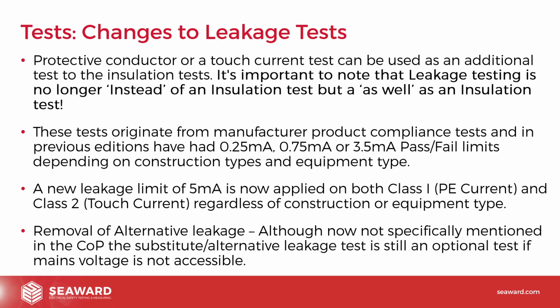The new leakage limit for the 5th edition code of practice is now 5 milliamps, and this applies to both Class 1 and Class 2. So it's just a 5 milliamp limit, whether that's a PE current test or a touch current test, whether it's portable, handheld, movable, stationary, whatever the type of equipment is. We now just do a leakage test, and the limit is 5 milliamps. So we've got a 5 milliamp leakage limit applied to everything. That's quite a big change, going from 0.25 all the way up to 5 milliamps.